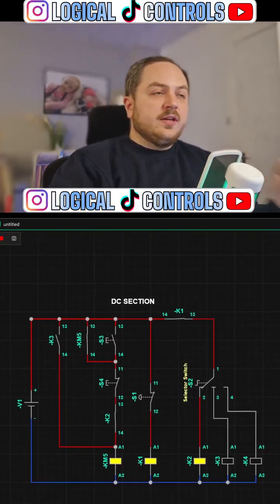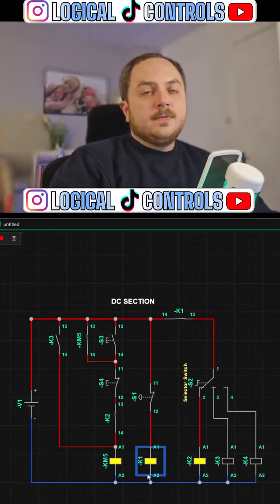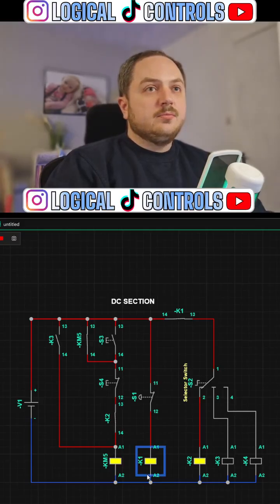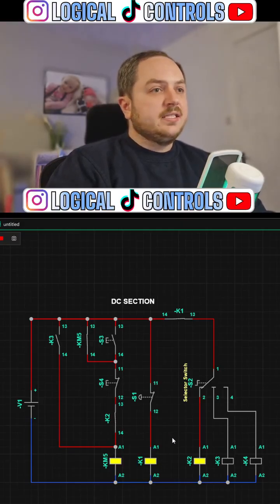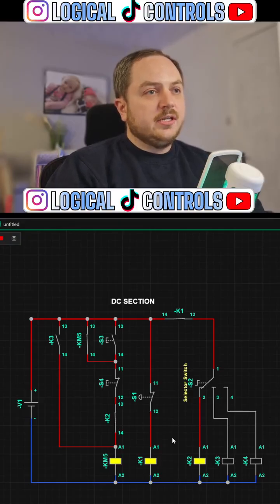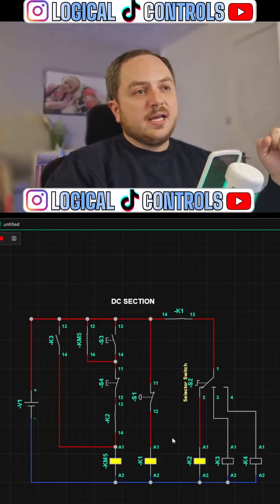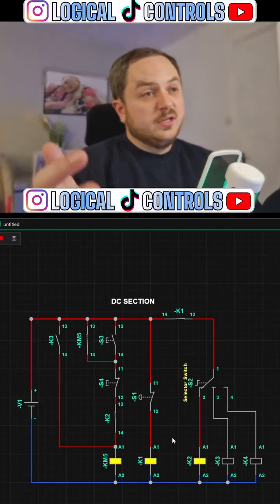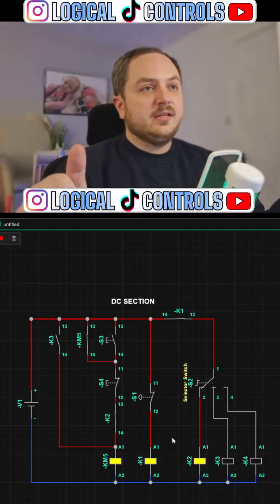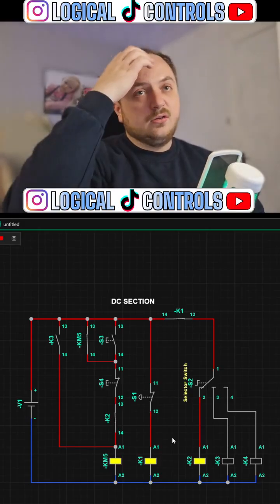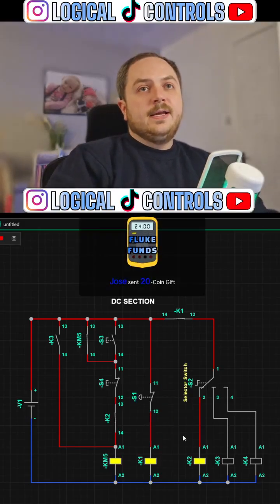Oh, one other thing I've not shown you. So sometimes what you'll find is some circuits have like a master trip relay. And what that basically is, if there's some sort of emergency or something, you slam like an e-stop. That's what I'm doing in this example, but it could be really anything, depending on the circuit or the application. So you can see all my control circuit.